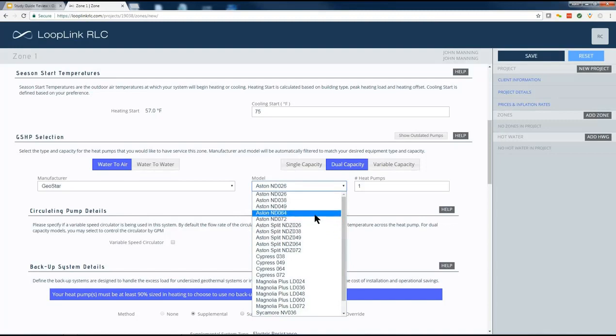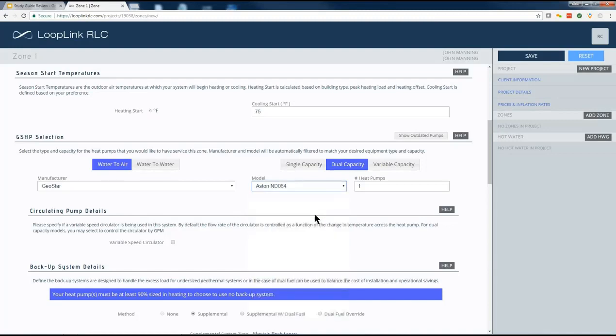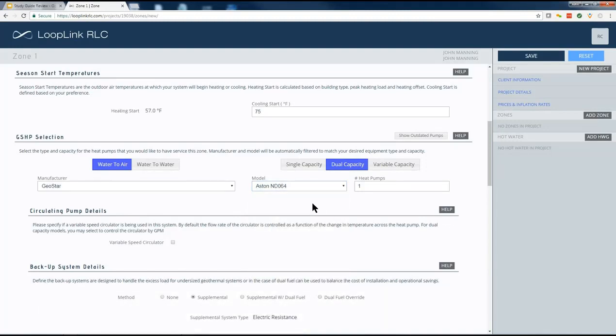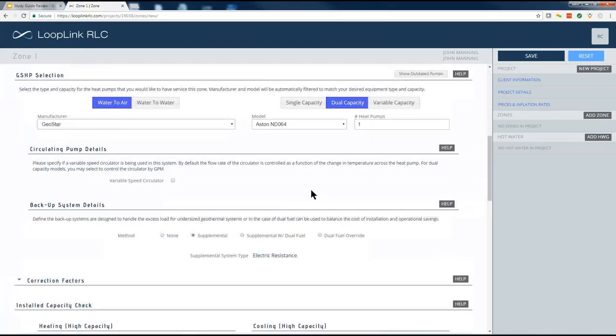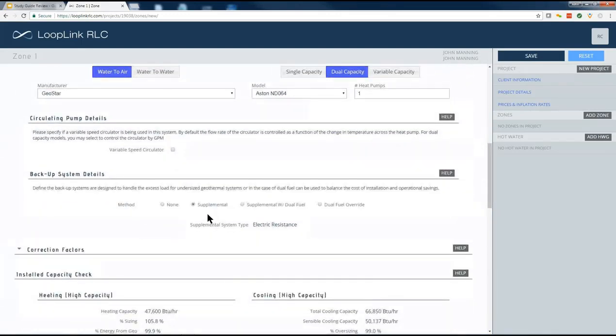We can go ahead and grab a unit. Let's go ahead and, for the sake of example, take a look at a 5-ton unit just to start out and see where we end up. Keep in mind that with a 30-degree minimum EWT value, you only get about 80% of the rated capacity off of the unit. So this being a 5-ton unit with a 30-degree loop, you're probably going to get between 45 and 50,000 BTUs per hour of actual heating capacity under design conditions.